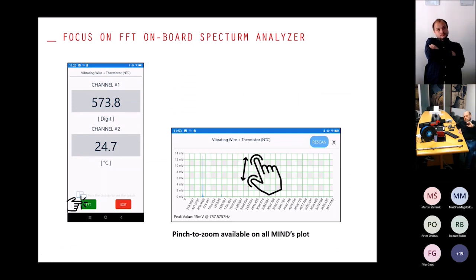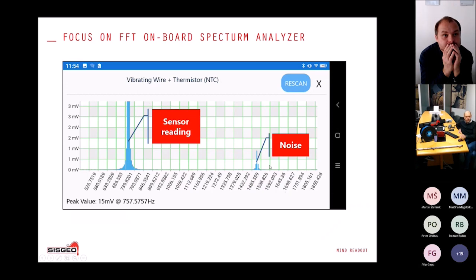Another focus is the spectrum analysis of the vibrating wire sensor. When you are on the reading screen for the vibrating wire sensor, just push the FFT button, meaning fast Fourier transform, and the plot of the spectrum analysis appears. You can pinch to zoom the plot, and you can see, for example in this case, the sensor reading the main wave along with a small noise. This tells you that at the position where your sensor is installed, there is something causing noise to your sensor. This is very important for troubleshooting at site.